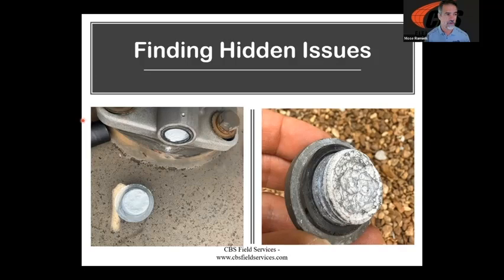You can see the corrosive dust that was created over time. By all estimates, this transformer hadn't been touched in 10 to 15 years. So once again, this problem has been hiding there, waiting for a moment to fail. And fortunately, the client started doing a testing program, and now we can head this off.